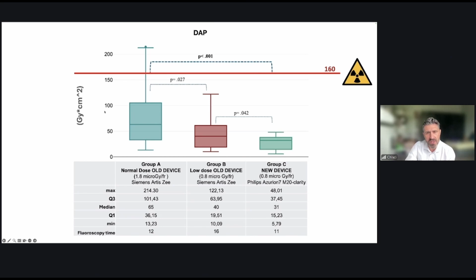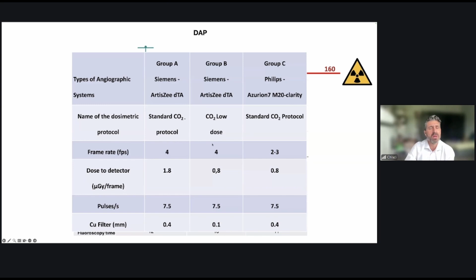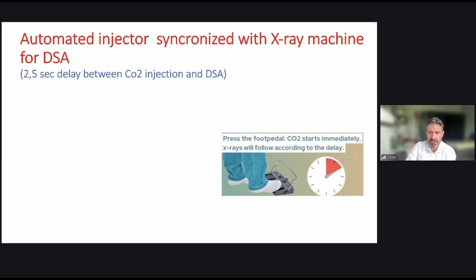But we are not happy because we know that we should have the lowest dose possible. This is the parameter that we set in our machines. So, is it possible to do better? Yes, for sure. The first optimization was to use the automatic injector synchronized with the X-ray machine. So you press the foot pedal, the CO2 starts immediately, but the X-ray will follow according to the delay.